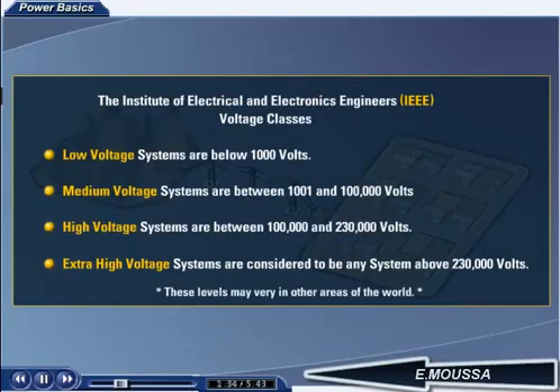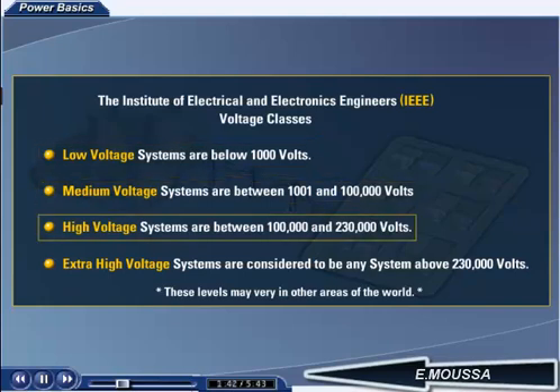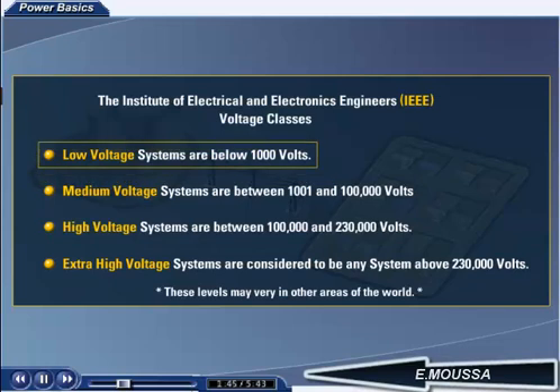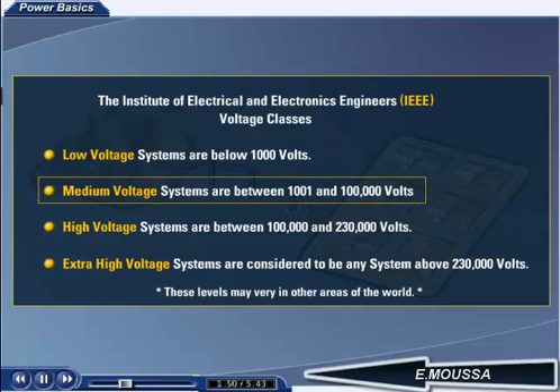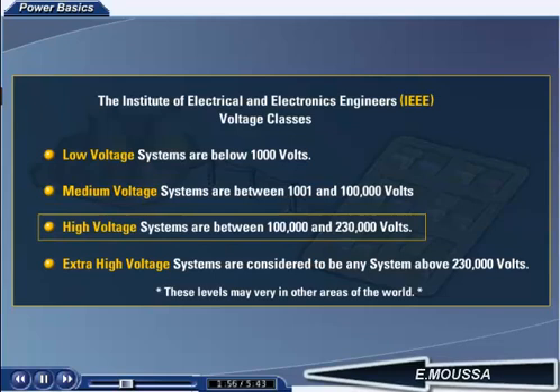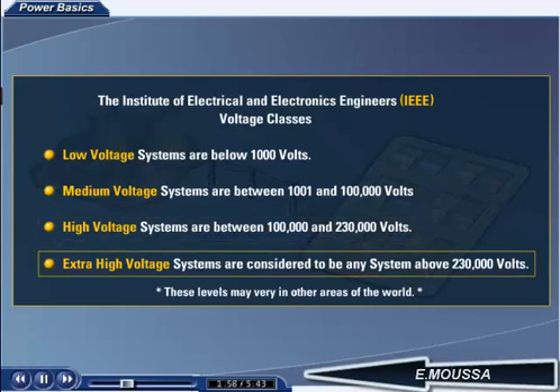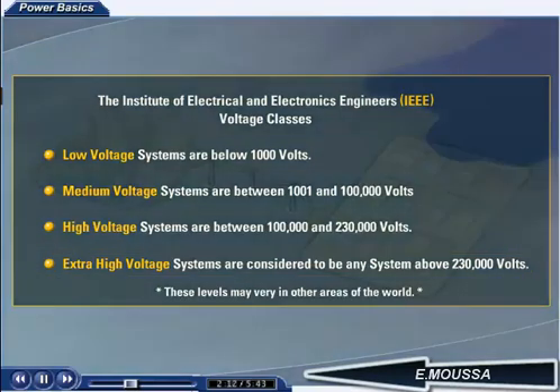The Institute of Electrical and Electronics Engineers, sometimes referred to as the IEEE, have divided voltage systems into low, medium, high voltage, and extra high classes. Low voltage systems are below 1000 volts. Medium voltage systems are between 1001 and 100,000 volts. High voltage systems are between 100,000 and 230,000 volts. And extra high voltage systems are considered to be any system above 230,000 volts. The voltage levels may vary in different parts of the world, but the names of the classes for the most part remain consistent.